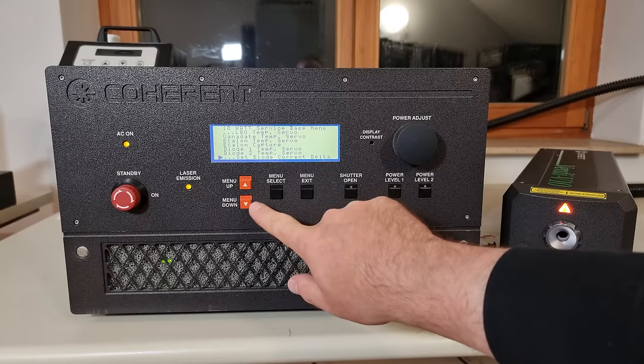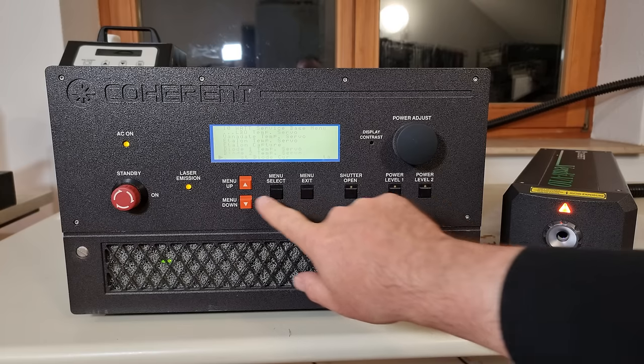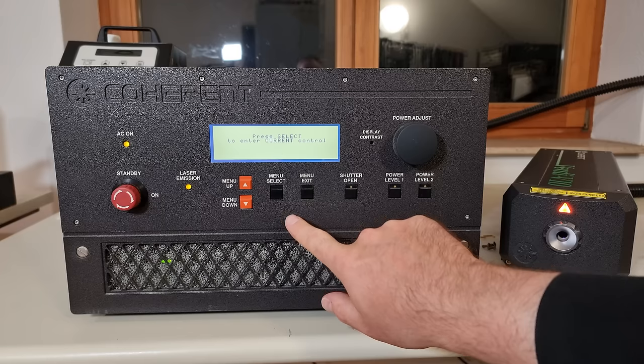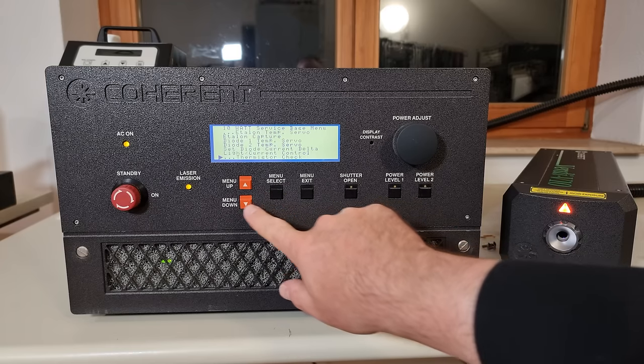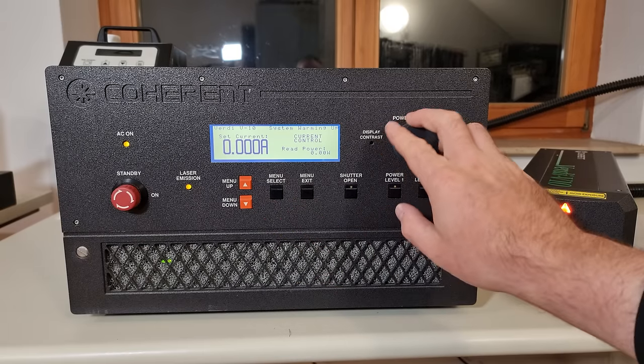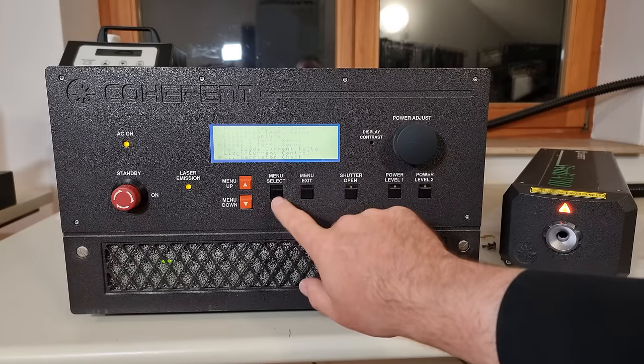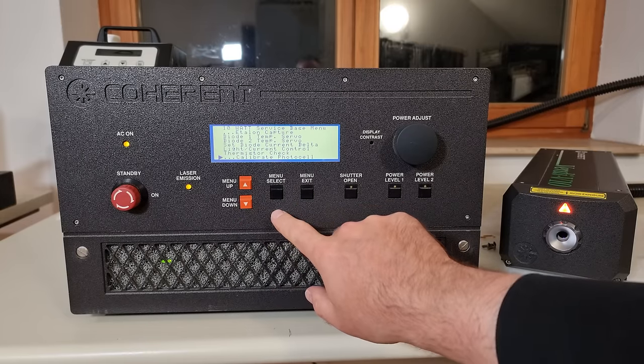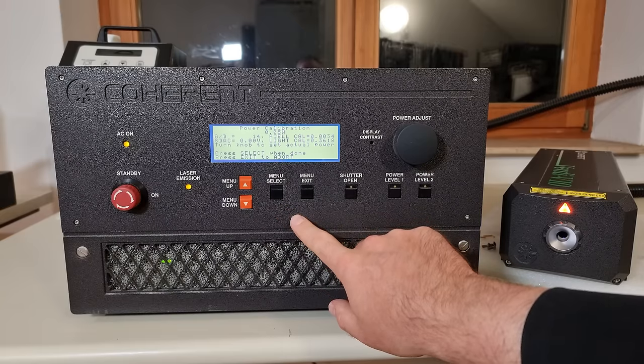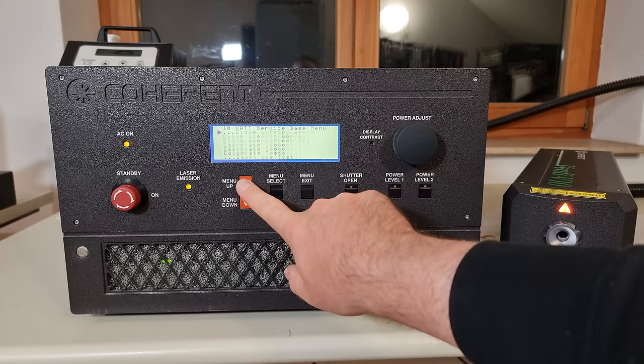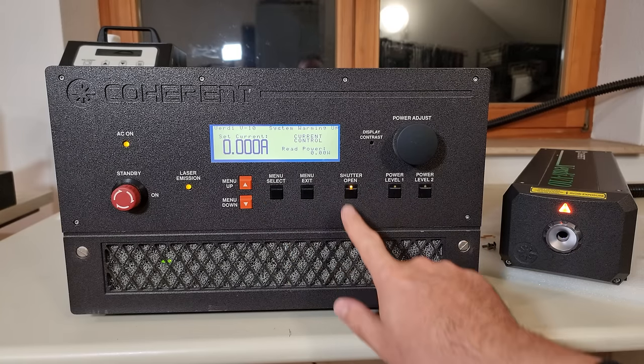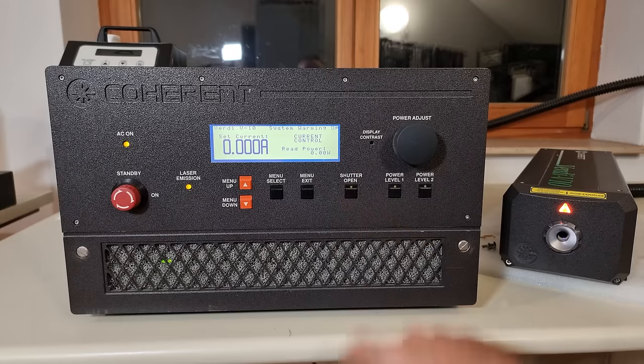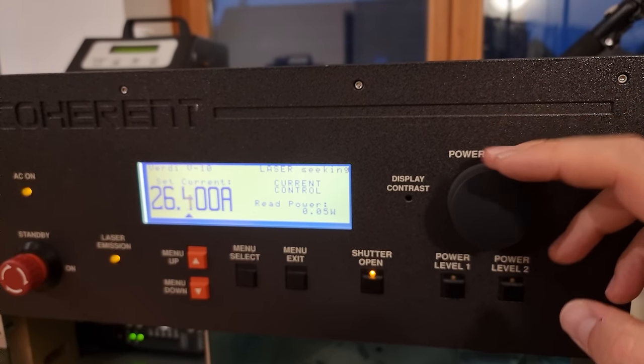With diode current delta, you can force a small asymmetry onto the diode's power supplies to try and compensate for other imbalances in the system. Here I'm going to switch to current control mode, which lets me command with that power adjust knob on the right, how many ampere are going to be squeezed through the diodes. As opposed to the default arrangement of me commanding how many watts of output power I want, and the Verdi trying to deliver that based on a built in power sensor. Which should be right there in the head, just behind the brightly illuminated warning sign. Um, okay, I think it's time to get out of the way, lest we are pew pewed out of existence in a moment. Yep, that's my small contribution to optimism today.